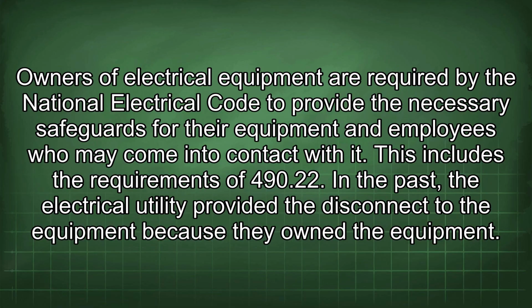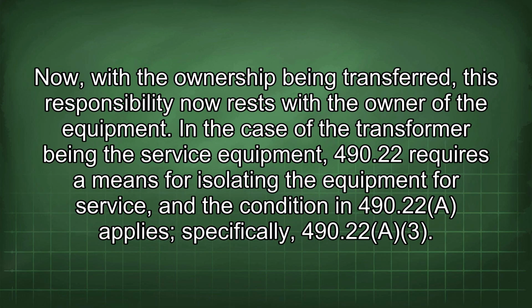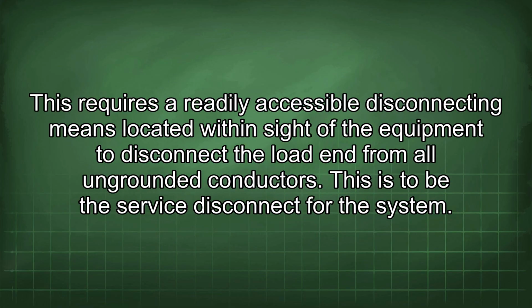490.22. In the past, the electrical utility provided the disconnect to the equipment because they owned the equipment. Now, with the ownership being transferred, this responsibility now rests with the owner of the equipment. In the case of the transformer being the service equipment, 490.22 requires a means for isolating the equipment for service, and the condition in 490.22 applies, specifically 490.22(A)(3). This requires a readily accessible disconnecting means located within sight of the equipment to disconnect the load end from all ungrounded conductors. This is to be the service disconnect for the system.